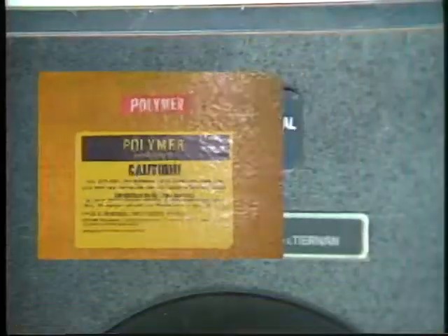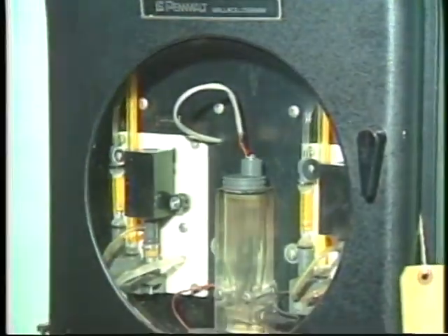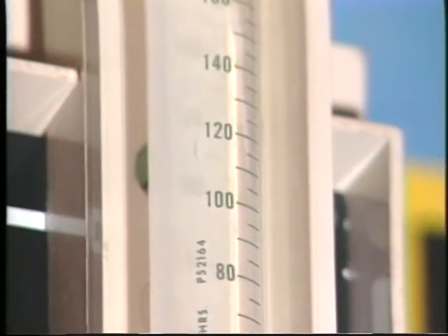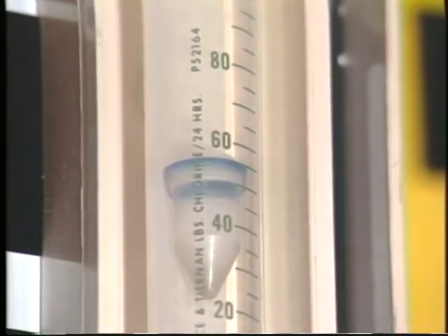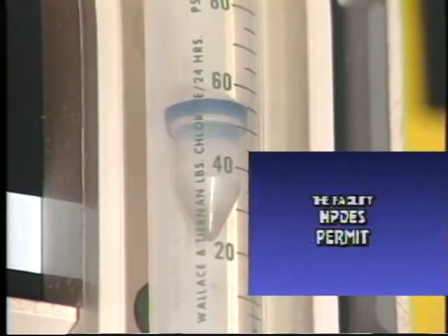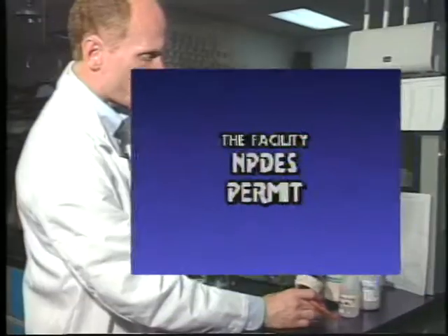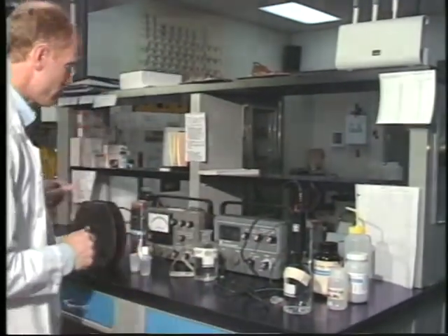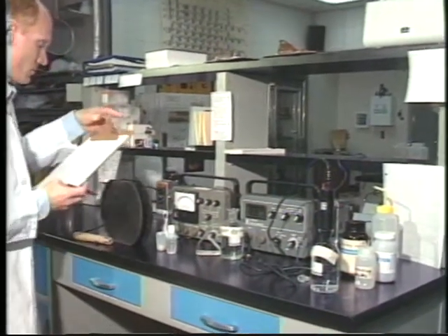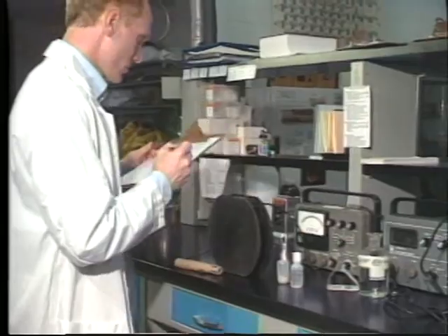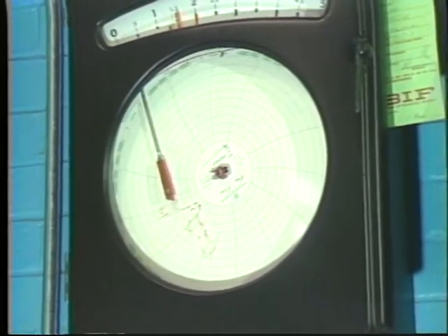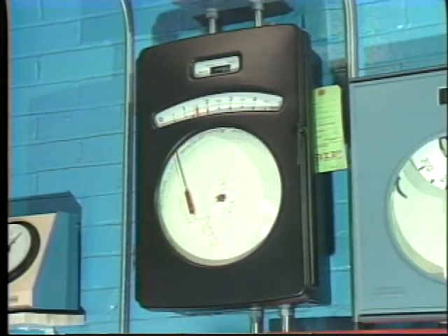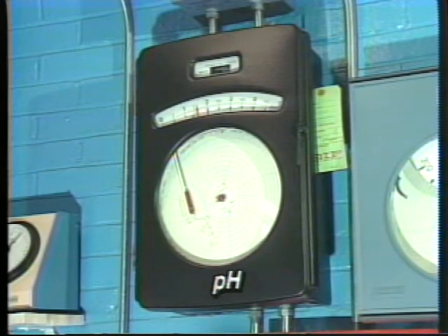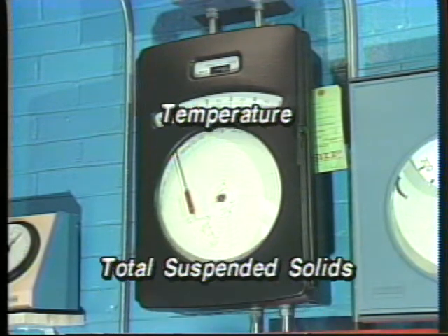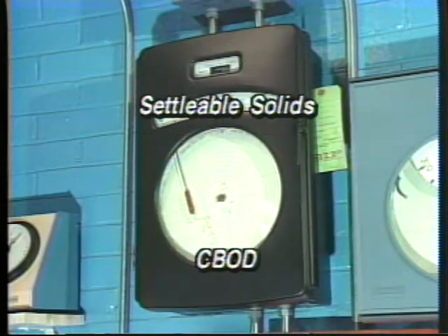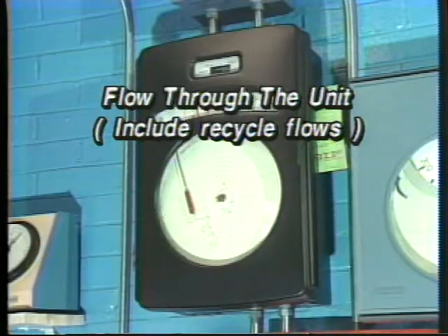For wastewater that exhibits septic conditions, the use of oxidizers such as potassium permanganate or chlorine may help to freshen the wastewater, reduce odors, and oxidize objectionable pollutants in the wastewater. The facility NPDES permit specifically requires the operators of the treatment plant to be familiar with operation and efficiency of each treatment unit. To meet this requirement, operators must perform and analyze process control tests. At a minimum, the lab tests and data on both the clarifier influent and effluent for calculating efficiencies and removals would include pH, temperature, total suspended solids, settleable solids, CBOD, and flow through the unit. Be sure to include recycle flows.